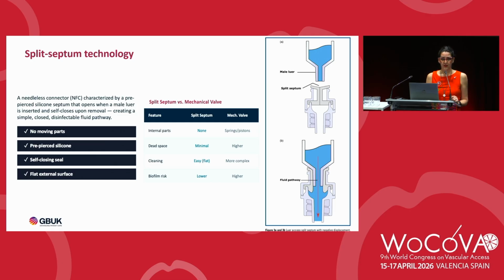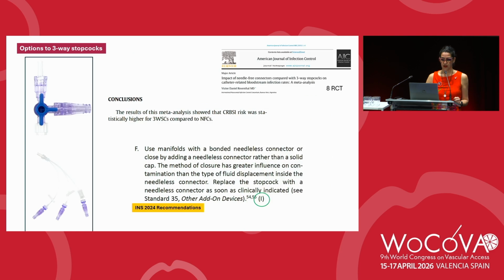Also, the split septum technology is important when talking about needle-free connectors because it's the simplest way to design one. We don't have any mechanical part inside the device, so no moving parts. We have a pre-pierced silicone membrane that opens once the syringe or the infusion goes in, and that self-closes once the disconnection is done. It is also very important for infection prevention because it has a flat external surface. So split septum technology is really quite good. As Giancarlo said, you have many options nowadays, so it's not acceptable to not use needle-free connectors anymore.